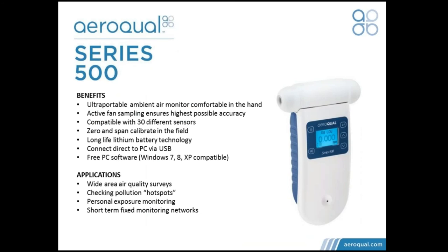That brings us to our final solution: an ultra-portable solution for air quality measurement. Aeroqual has been manufacturing portable instruments for measuring gases in the air for about 15 years, with more than 10,000 of these instruments in use around the world. What's unique is the ability to measure a whole range of gases through interchangeable sensor heads on a single base. The base can do a zero and span calibration in the field, or a bump test. It has a long-life lithium battery, and you can connect it directly to a PC to download the stored data.